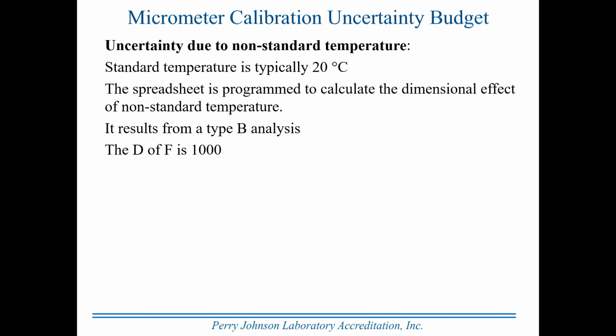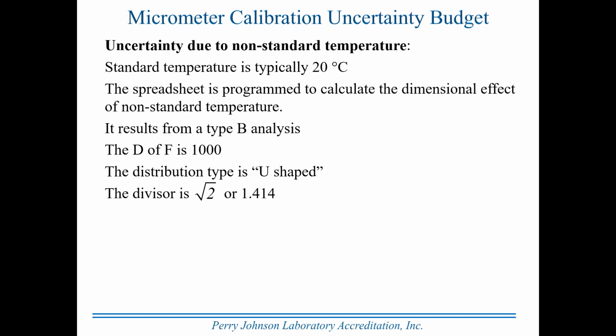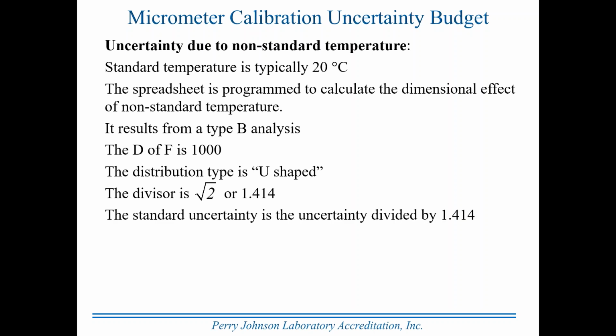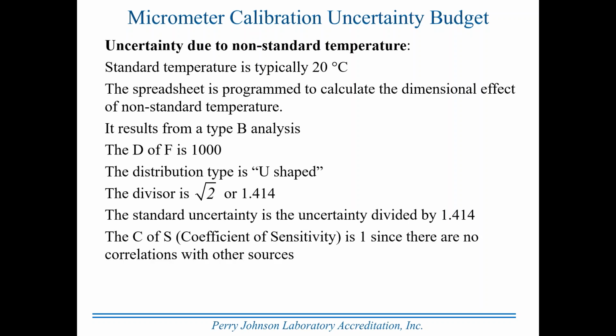Results from, again, type B analysis. Degrees of freedom is 1,000. Distribution type is U-shaped. It's not uniform, it's not rectangular, it's not normal, it's U-shaped, which means that you have very few values that occur in the middle, and most values occur at the extremes. So instead of the curve having a peak in the middle, it has a peak at both ends and a valley in the middle. The divisor for that type of distribution is the square root of 2. So again, we would take the half interval, divide by the square root of 2, which is equal to 1.414, and that would be the standard uncertainty due to non-standard temperature. The standard uncertainty is divided by, again, the square root of 2. Coefficient of sensitivity is 1 since there are no correlations with other sources.